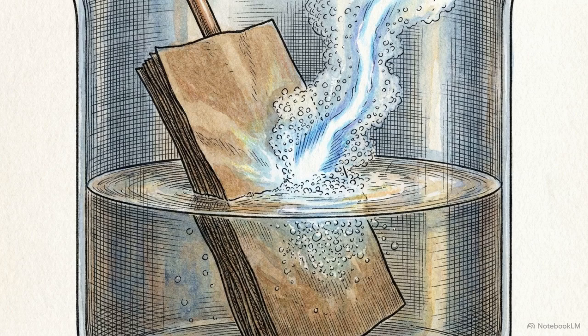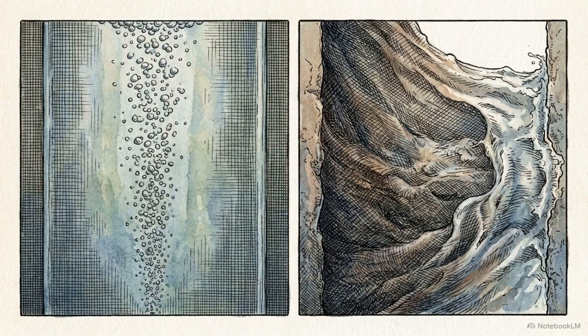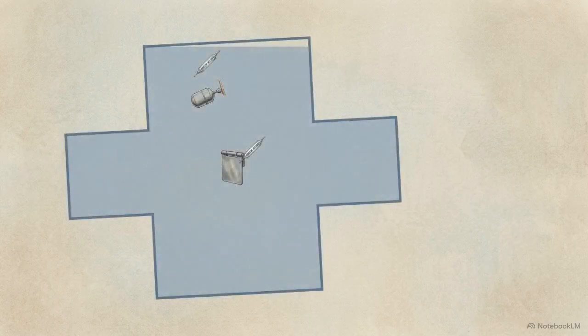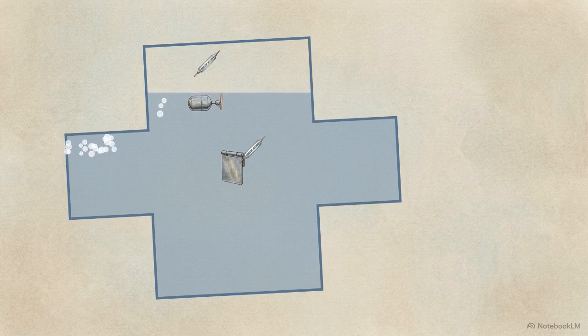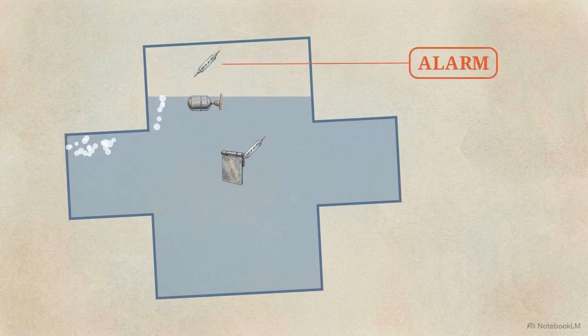Every internal electrical fault decomposes the transformer's solid paper or liquid oil insulation. That chemical breakdown generates either slow gas bubbles or violent pressure waves. This diagram shows an incipient fault. As insulation slowly cooks, gas bubbles travel up the sloped pipe and rise into the relay. The trapped gas displaces the oil, causing the upper internal float to drop. This mechanical action closes an isolated magnetic reed switch, sending an alarm to the control room.